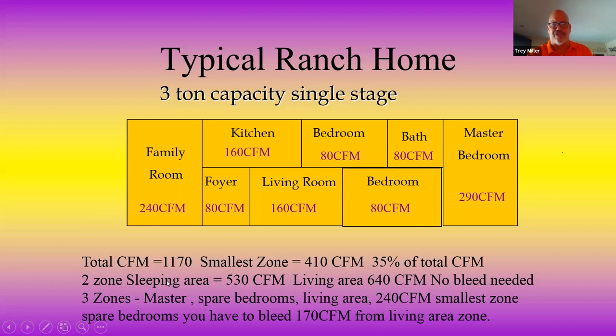If I want a two-zone system, my sleeping area is 530. My living area is 640. Both 640 and 530 are above 410, gentlemen, you put in a two-zone zoning system, no bleed, you're ready to go. But now let's take it a step further. Let's give us a zone in the master bedroom. Now, if I have a master bedroom, spare bedrooms, and living area, my smallest zone in the house now is 240 CFMs. That's these three rooms here, okay?